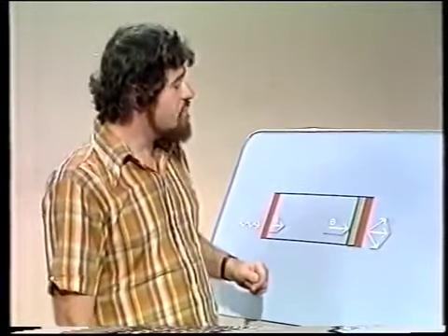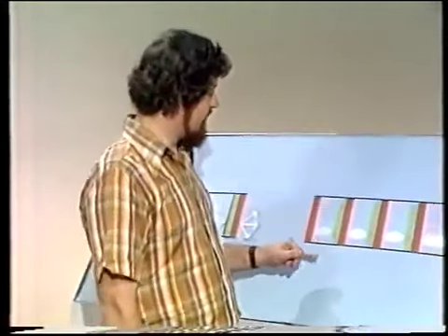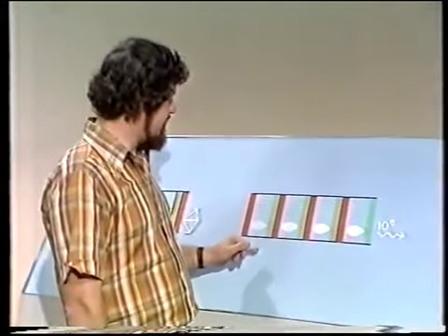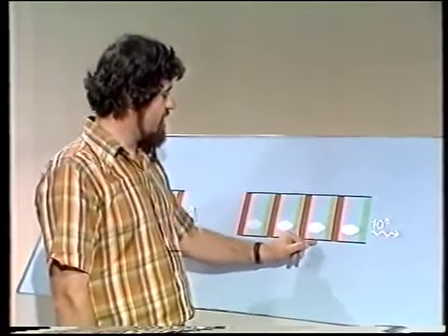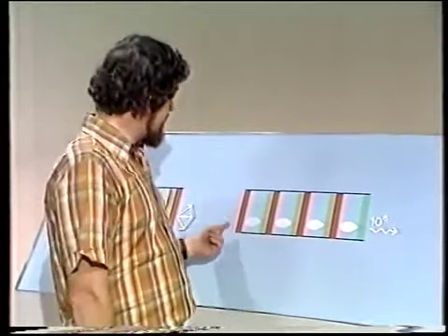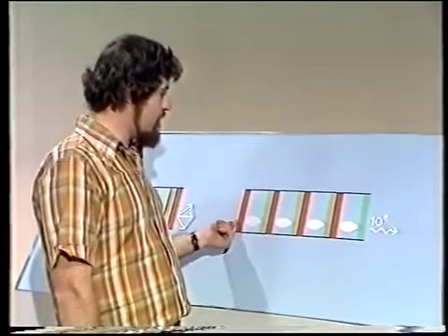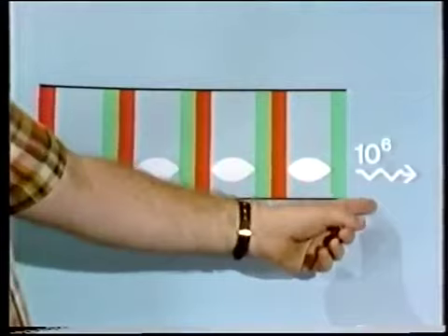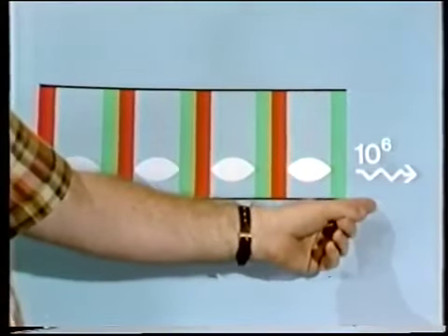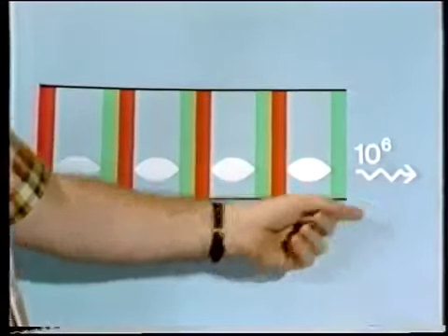Now, in fact, we do this more than once, typically 4 times, so there are 4 stages to the amplification. 1, 2, 3, 4. And the overall effect is to convert the single photon coming in to typically more, or at least, 1 million photons coming out. Well, that's the principle. Let's have a look at the hardware. And here is a piece of the hardware. In fact, it's a commercially produced image intensifier. The photocathode's down this end and the phosphor's at the other.